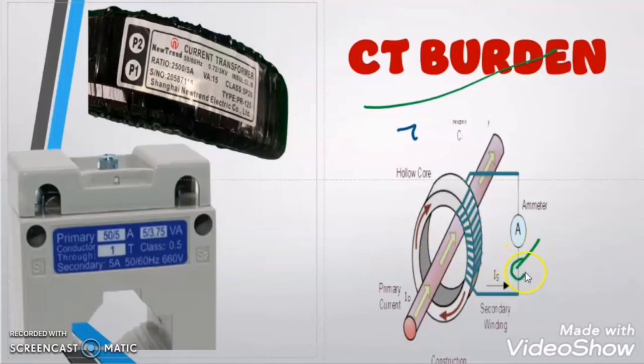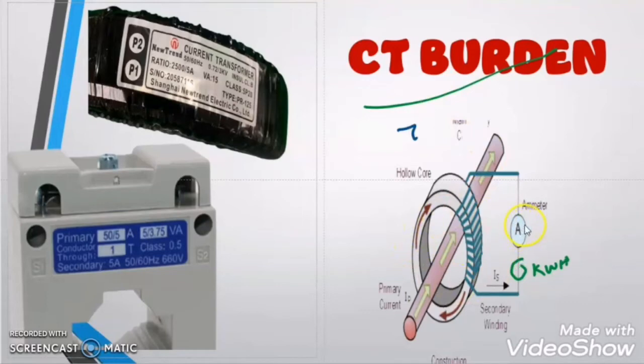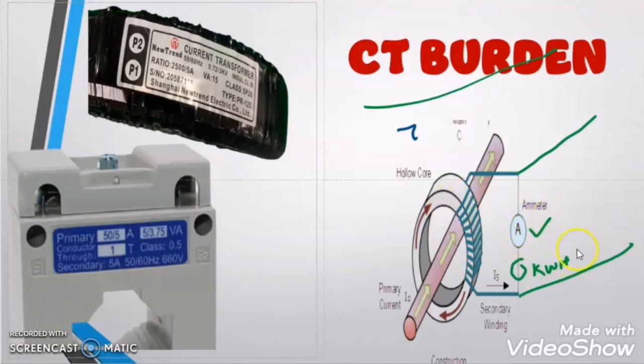For example, if we connect one kWh meter in series with the ammeter and it is connected with the same CT, then this ammeter plus kWh meter is called CT burden for this current transformer. Suppose this ammeter and kWh meter are not connected very near to the current transformer but are connected very far from it. Then the burden on this CT is due to this ammeter, due to this kWh meter, and due to the resistance of the wire connecting this ammeter and kWh meter through the secondary winding of the CT. CT burden is nothing but the total load connected to the secondary winding of the CT.